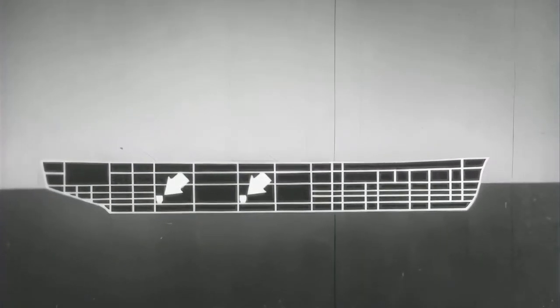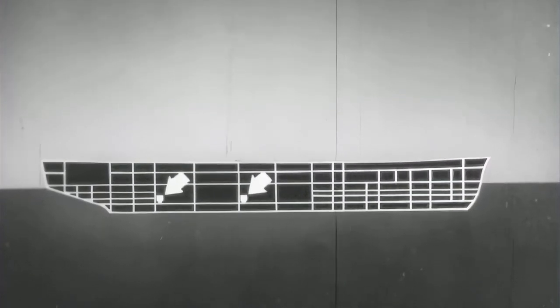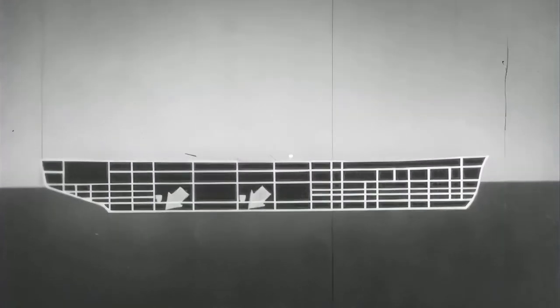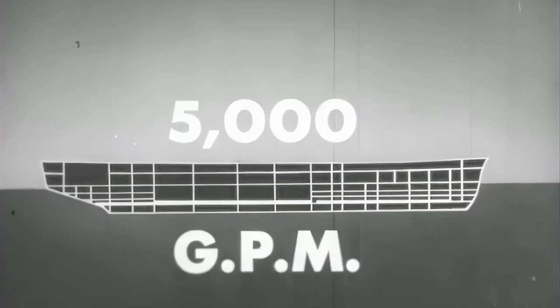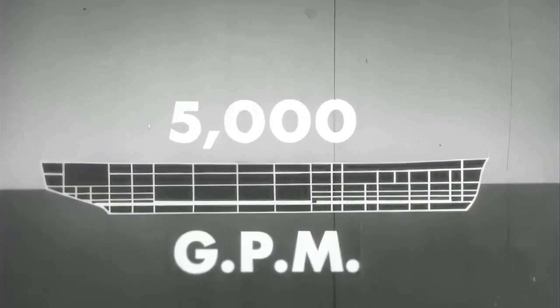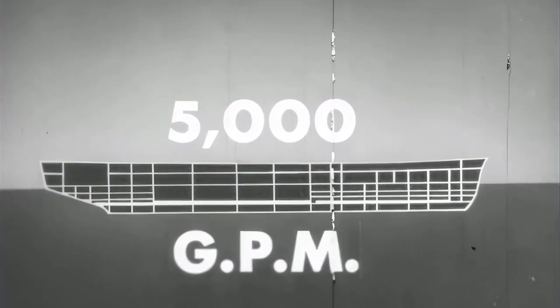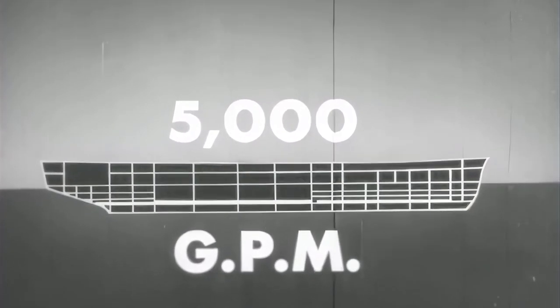The main condenser circulating pumps have large capacities, but their use for drainage is limited to the engine room bilges. Approximately 5,000 gallons per minute is the total installed capacity of the main and secondary drainage system on the newest cruisers. However, this capacity cannot be concentrated on any single flooded space. By comparison, a hole only a foot square and 15 feet below the waterline will admit nearly 14,000 gallons per minute. The installed main drainage system alone can't handle this quantity of water.